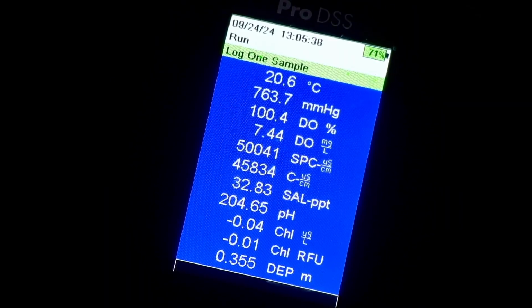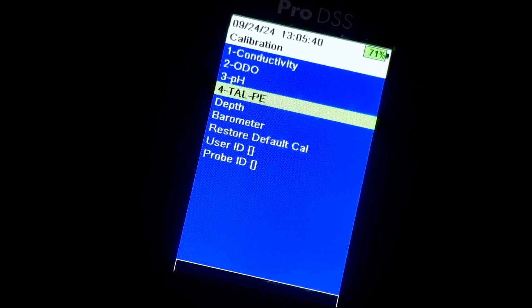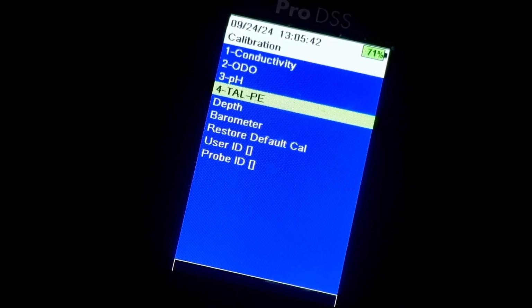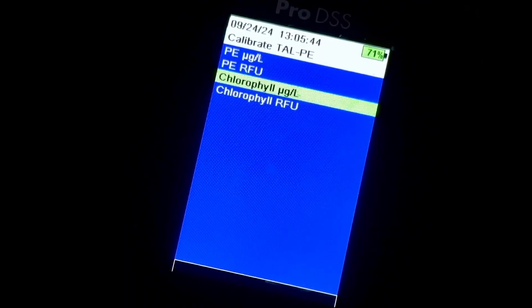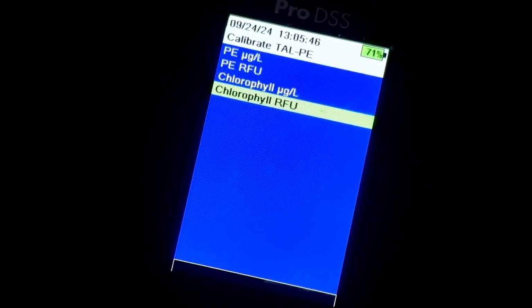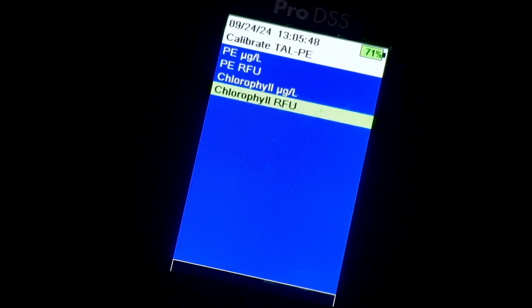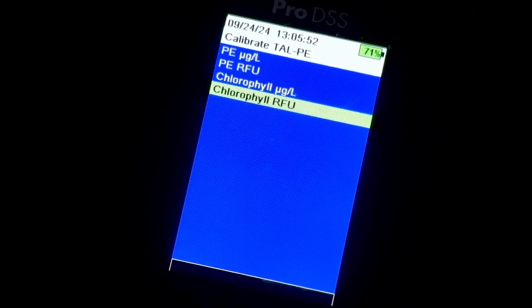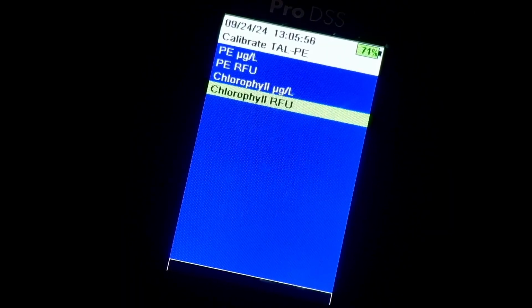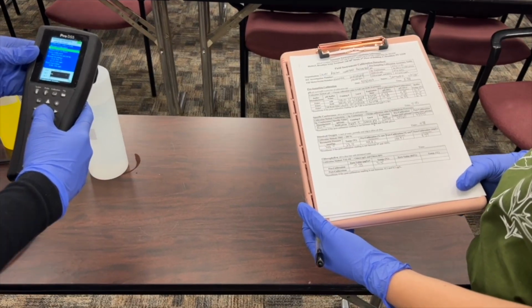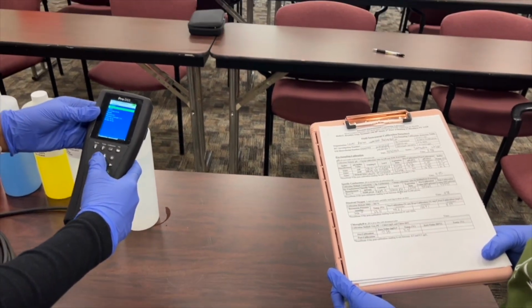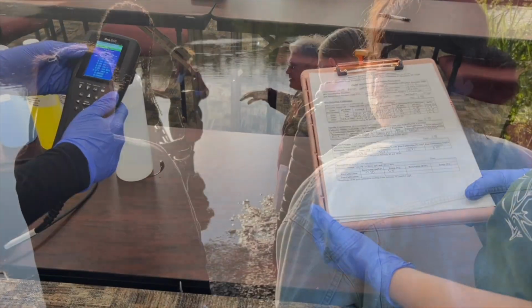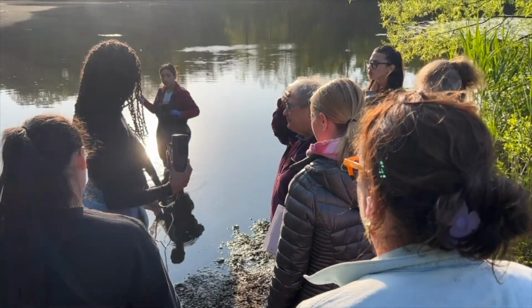Now, the last and most important step is to repeat the calibration for chloro-RFU. Chloro-RFU stands for Relative Fluorescence Units. It needs to be calibrated twice, and the post-cal values should be between -0.3 and 0.3 for both units. Once you're done, record the time and if any recalibration was done. That's it. Now you're ready for monitoring.